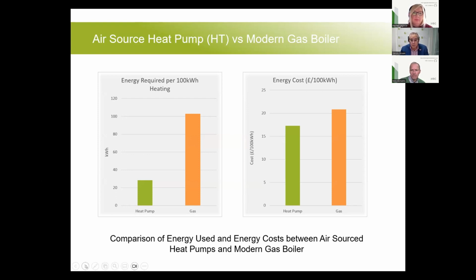So that second graph is now looking at the cost to provide 100 kilowatt hours of heating. On the green, doing the maths, 38.5 divided by 3 times 60.5 times 100 comes to £17.28. And then the gas boiler, 100 kilowatt hours times 20.2 pence, with the 94% efficiency, comes out at £20.82. So you can see that even at that efficiency, it's still cheaper to run an air source heat pump.